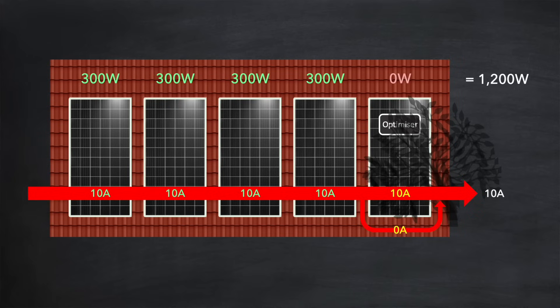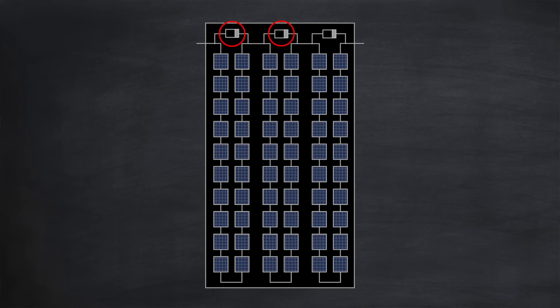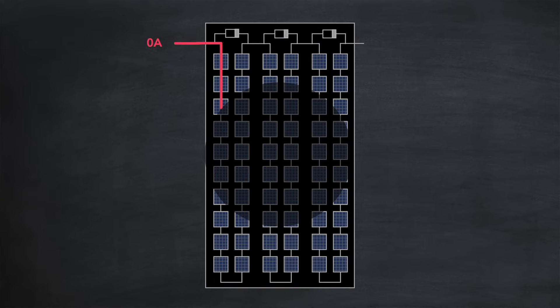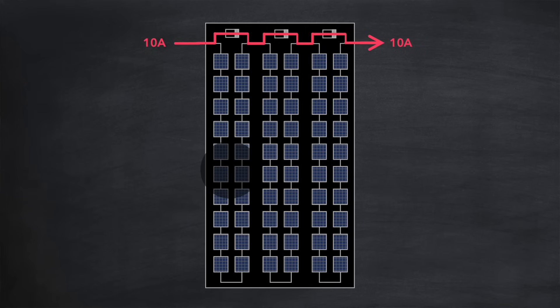Let's remove the optimizer to see if we can figure that out. Nothing changes — how can this be? Well, remember those little components called bypass diodes. Despite their small size, they actually perform a similar function to an optimizer. If these diodes detect a blockage in current within the cells they're managing — typically anything above a 20% reduction in current — they will bypass all of the current around those cells. And because there are three bypass diodes, each diode acts independently on a third of the panel. So if only a third of the panel is affected by shading, the remaining two-thirds can still generate power. Crude, but highly effective.